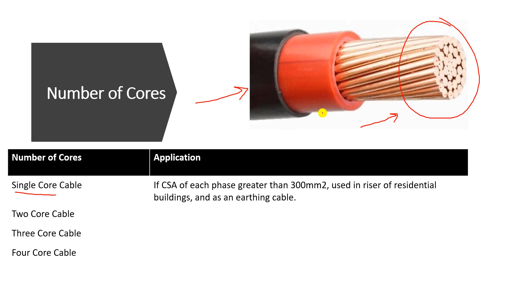Why do we use a single core cable? There are many cases. The first is when the cross sectional area of each phase is greater than 300 millimeter square. In a three-phase distribution network, if each phase has a large cross sectional area over 300 mm², we don't use a multi-core or three-core cable because it would be very large. So we use single core cables, each carrying one phase. It can also be used in risers of residential buildings and as an earth conductor cable.